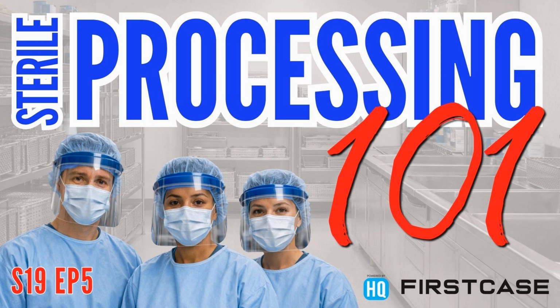So in an ideal world, we would just sterilize everything, right? Because that's the safest situation. But there are some instruments that can't handle the sterilization process. I'm thinking particularly of those large diameter flexible endoscopes that they use down in endo for doing a colonoscopy or something. The majority of those scopes can't handle the sterilization process. And so we high level disinfect them, which is appropriate for their use in just about every case, because they're not going into a sterile part of the body. And so we go with high-level disinfection.